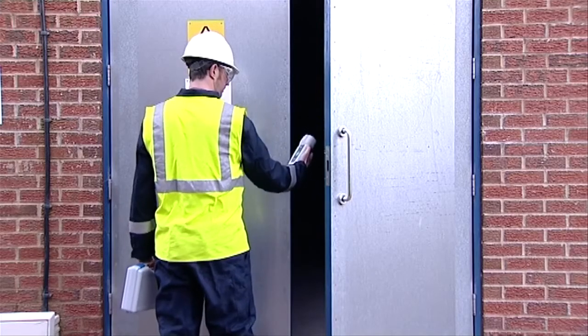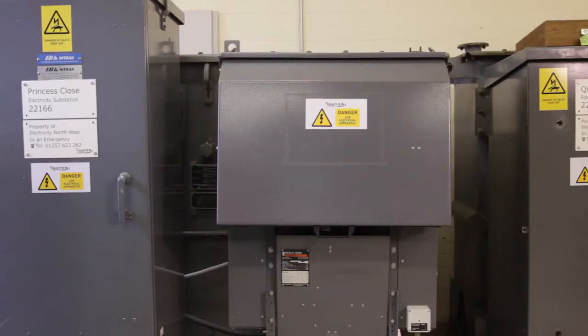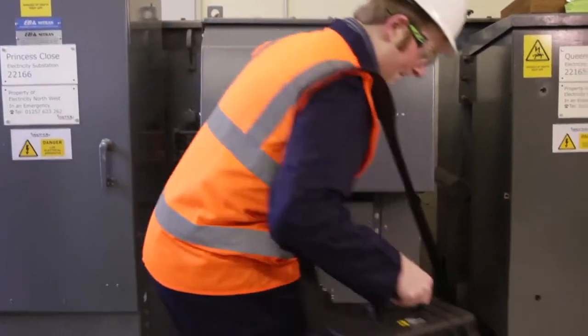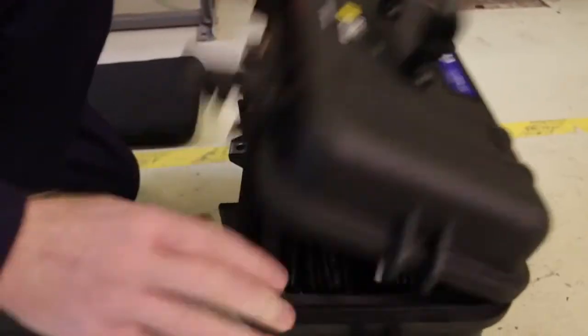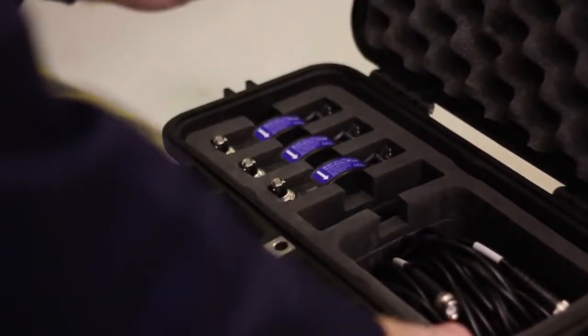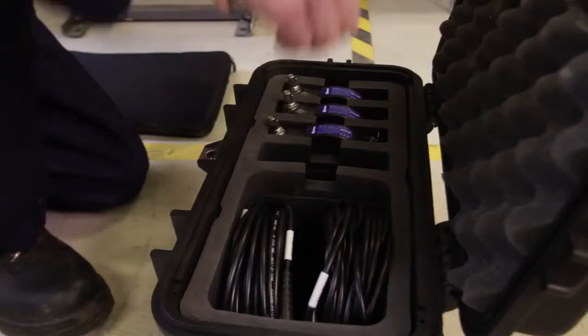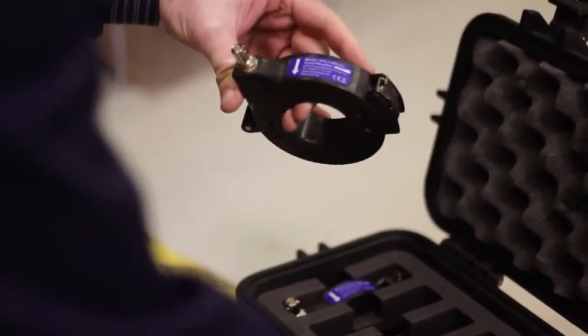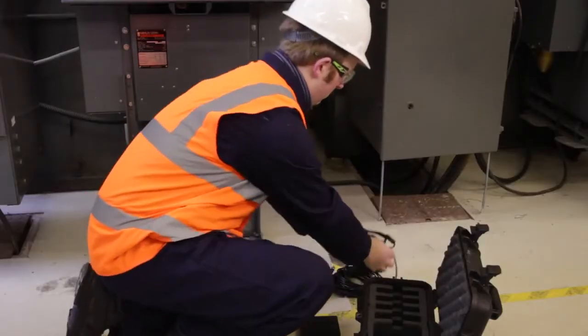Okay, safety first. It's always good practice to check out a substation for dangerous PD activity before you go in. The UltraTev detector or UltraTev Plus are ideal for this. Now let's see what's in the Cable Data Collector kit. The Cable Data Collector unit itself. 3 RFCT sensors, radio frequency current transformers, one for each phase. Cables. A phase reference transformer. Plus, you'll need a laptop PC for capturing the information.